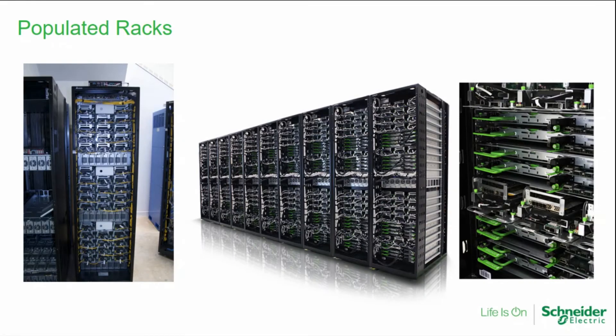Up on the screen we have some images of open compute IT hardware. At first glance it doesn't look terribly different, and it's not — but there are some key aspects. The rack in this case is still two feet wide or 600 millimeters, but the rails are actually a little bit further apart: instead of 19 inches, it's 21 inches. If you step back it almost looks like a regular rack.